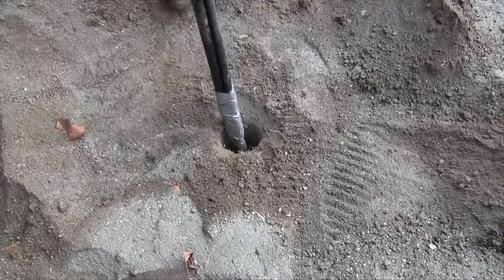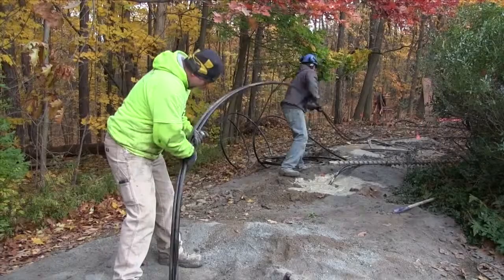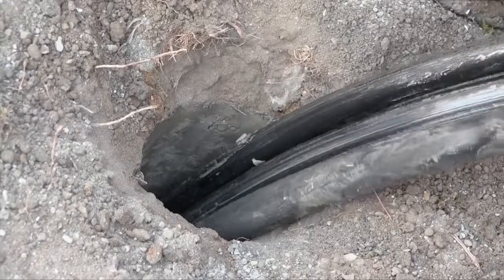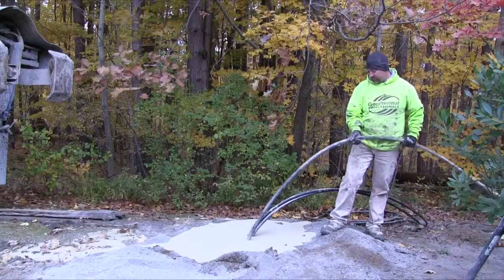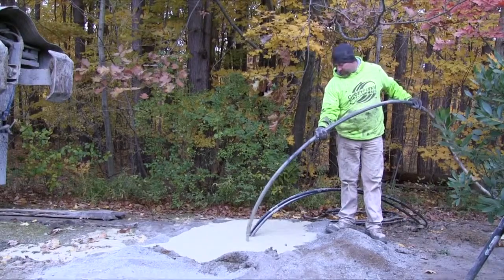What's different from what we do and what everybody else does is, first and foremost, we're installing a virgin 4710 resin high density polyethylene. Sounds technical, but what it means, it's a high grade, commercial grade tubing that has higher elasticity and greater strength. And we're also filling that void with a thermally conductive grout. It's a mixture of bentonite clay and silica sand. The silica sand serves to enhance the thermal conductivity of the earth to the loop, and the clay serves to seal the loop and seal the ground off.